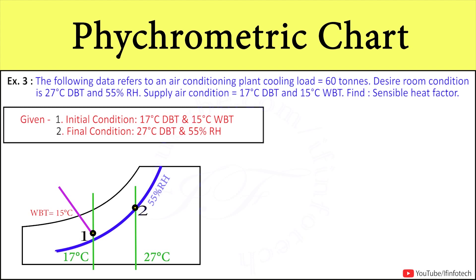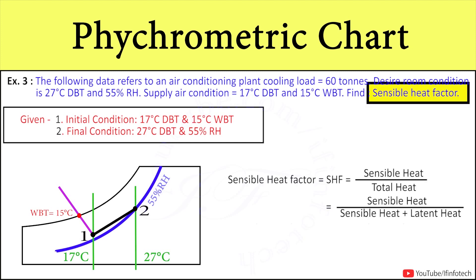As you can see, dry bulb temperature has been increased from 17°C to 27°C from initial to final condition. So we have the process 1 to 2, and in the problem we want to find out the sensible heat factor. Sensible heat factor is the ratio of sensible heat to total heat, and total heat is the sum of sensible heat and latent heat.